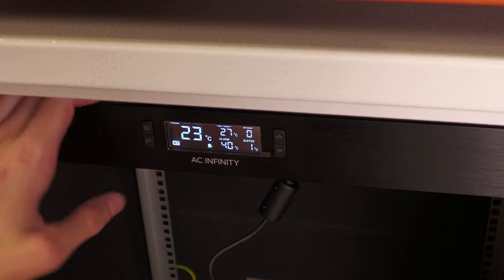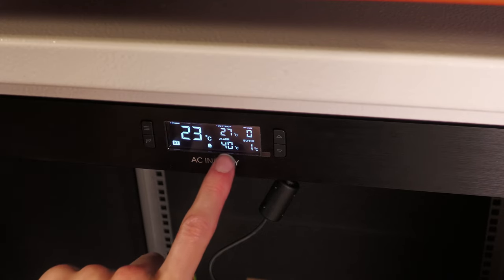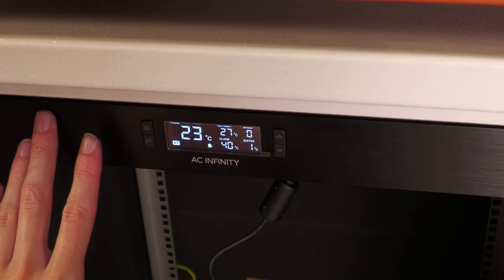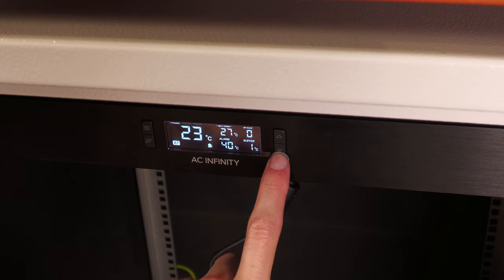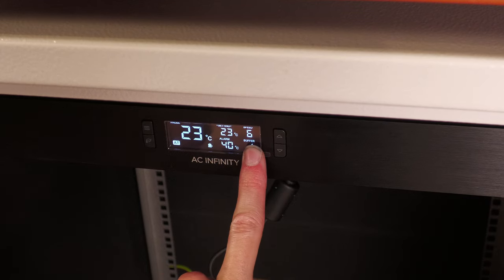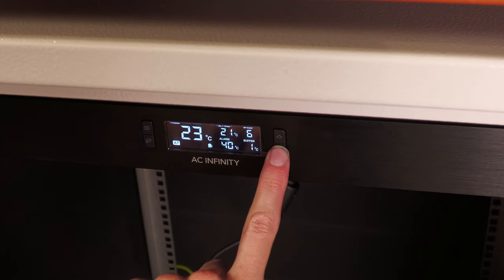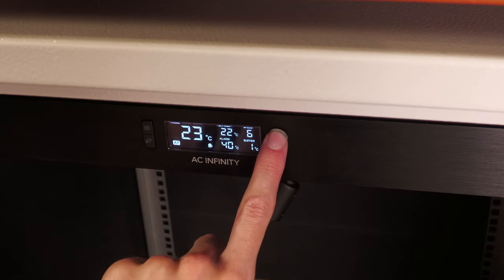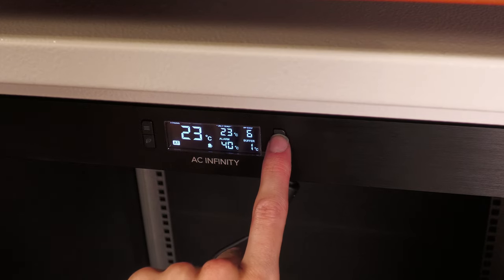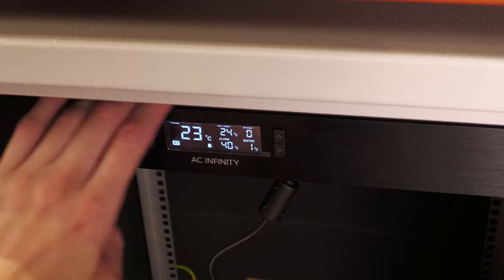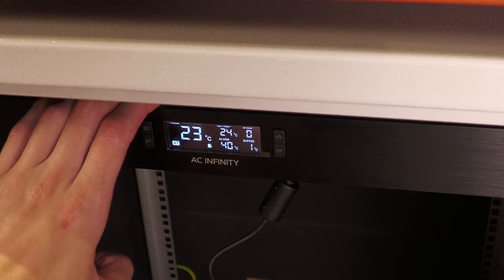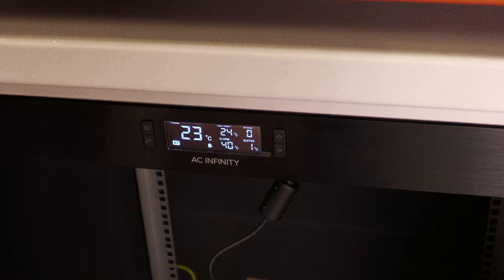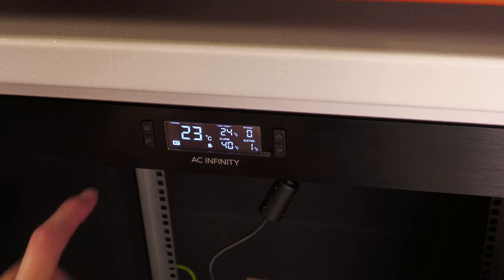This is a thermostat, so as you can see, the probe is sensing temperature 23, the setting is set to 27, fans aren't running, speed 0. If we start decreasing the set temperature, you'll see that eventually when we hit 23, the fans come on to full speed, and they'll continue to run at full speed no matter what the set temperature is. And as soon as we go above 23 on the setting, the fan speed drops down to 0 again. So that's just a thermostat, the fans will turn on and off on the thermostat. That's not what I want.